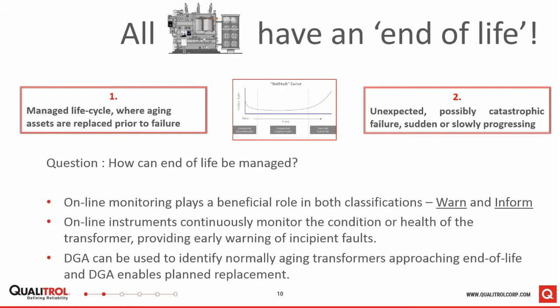In particular, for transformers, dissolved gas analysis is a very powerful tool for fault detection. It's been used by the power industry for the last 40 or 50 years. Not often deployed on vault transformers because of the difficulty of access to take out an oil sample. We have, of course, over the last number of years, and Qualitrol have, and you'll see it today, a product which is suitable for the vault application and can do dissolved gas analysis online.